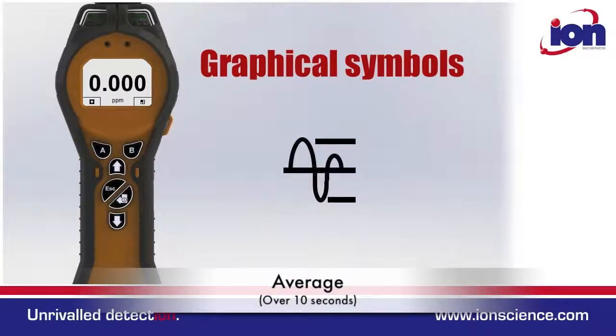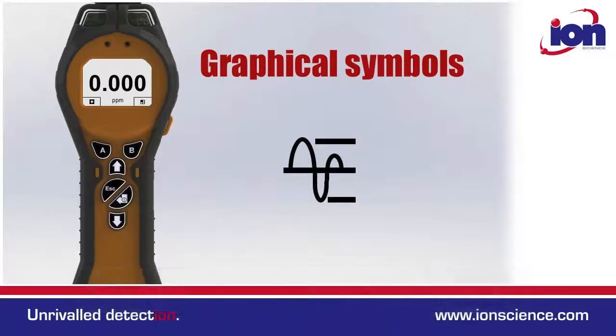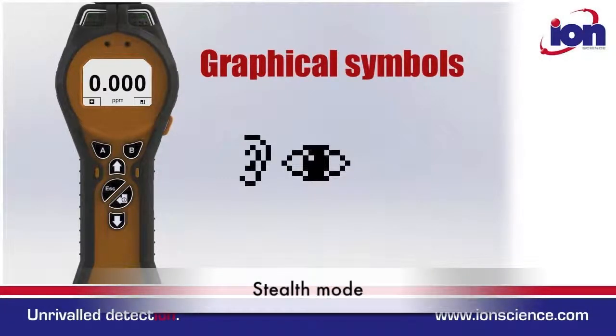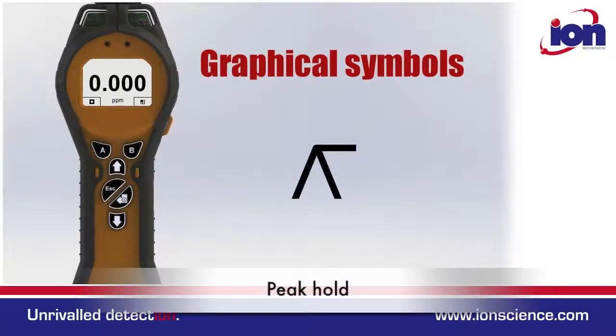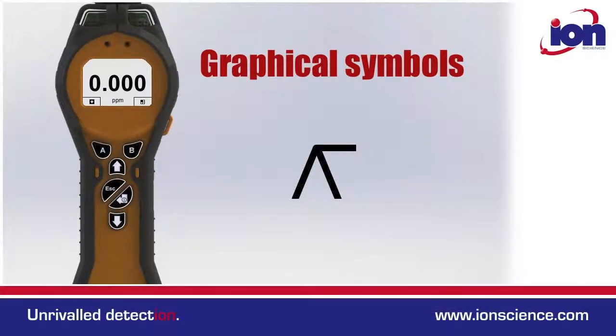Average: this gives an average reading over a 10-second period. Stealth mode: this disables audio and visual alarm indicators, so it avoids causing panic if you are in a public place. Peak hold: when selected, the highest measured reading is held on the display.